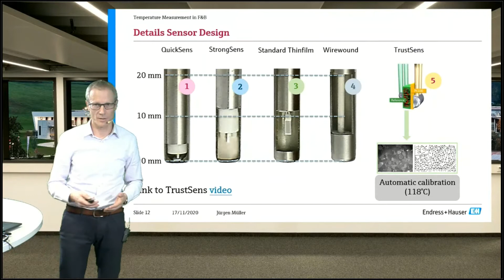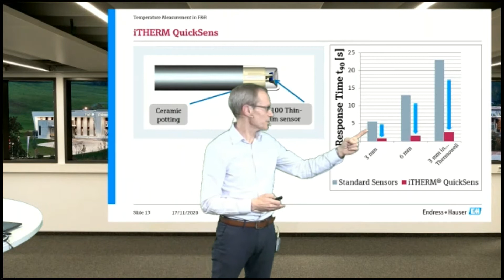Coming back to the QuickSens, I just want to show you this graphic here, where you clearly see that we managed to reduce the response time to levels where nobody else has been before and we haven't been before. With the QuickSens, if you use a thermometer with 3 millimeter diameter, you can reduce the response time to a value below 1 second, and it is 0.75 seconds. If you use a thermometer with a standard thin film sensor, with a 3 millimeter diameter, you have response times of around 5.5 seconds.